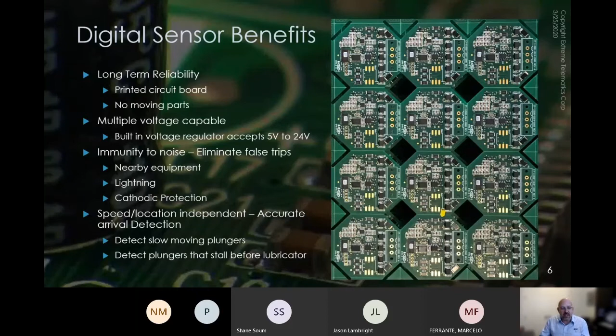It also becomes speed or location independent. As I mentioned, the amount of ferrous material in the plunger is what pushes and pulls the Earth's magnetic field. So whether it's slow, not even moving at all, or even if the plunger doesn't make it to the lubricator, we can still see the change that it started to create before it got there. So you don't have to worry so much about placement of an arrival sensor with this technology.